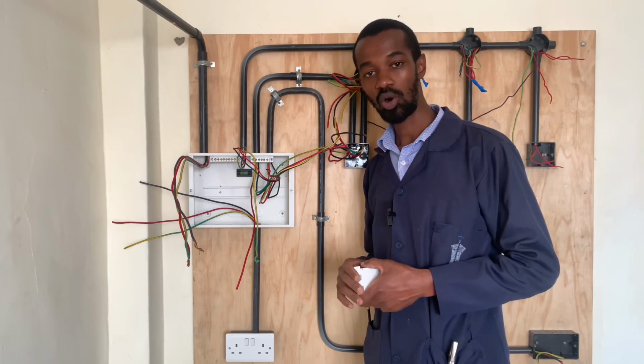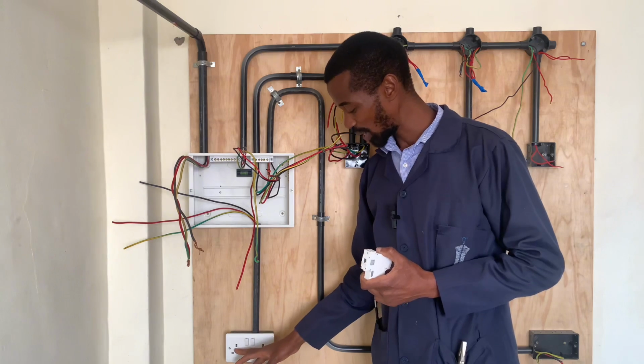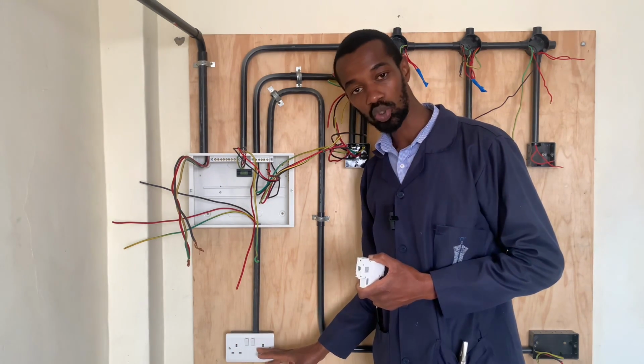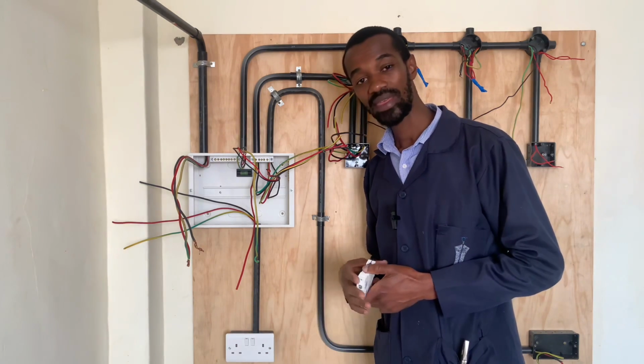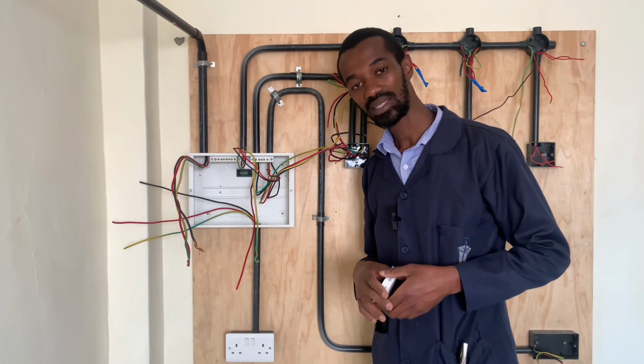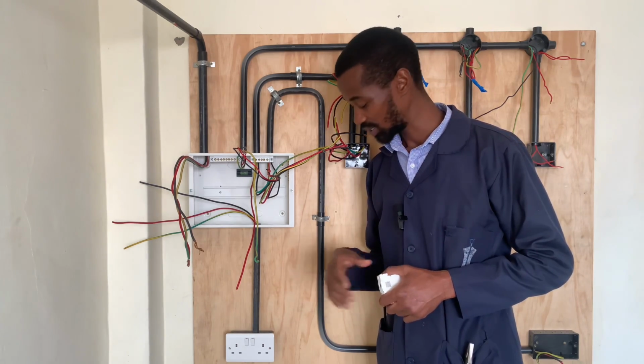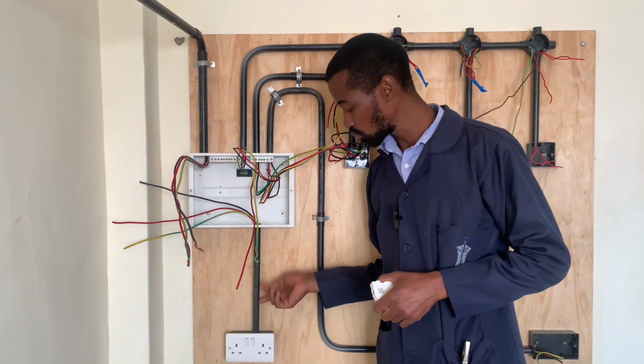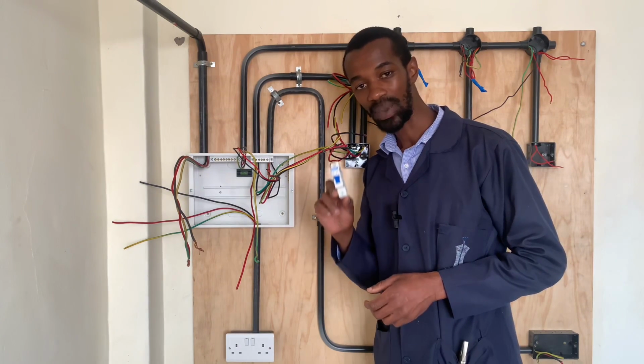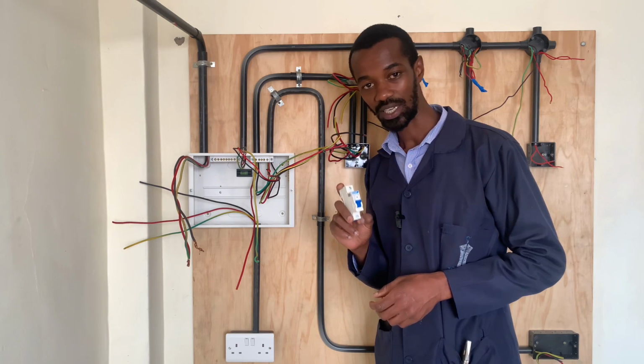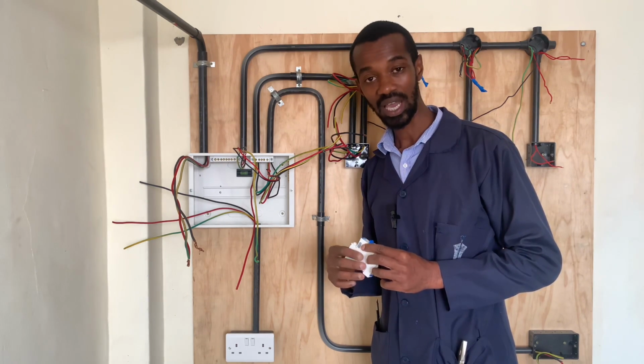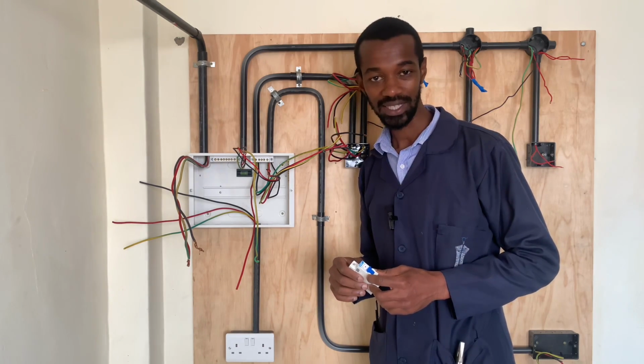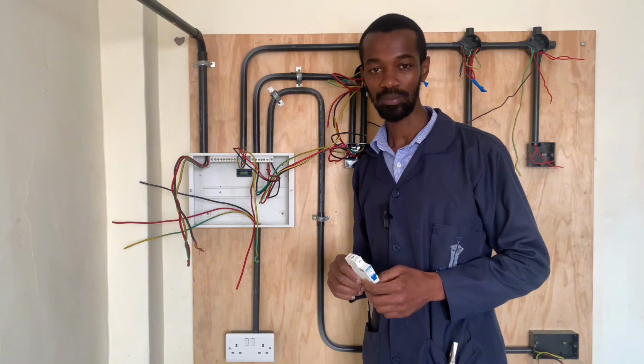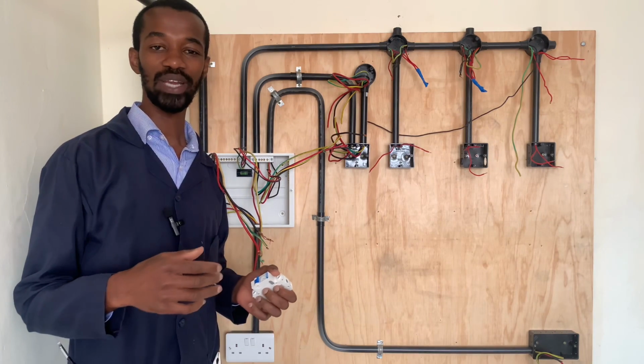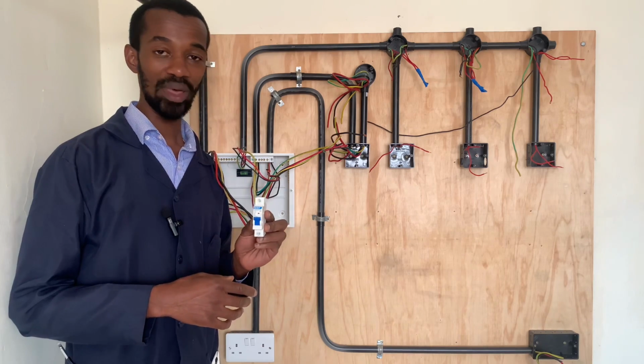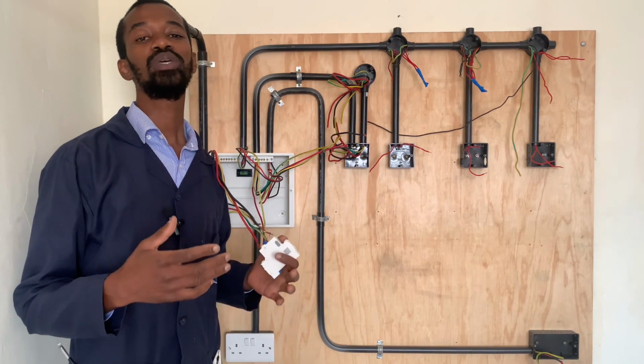The customer may decide to have a microwave on one plug and an extension cord on the other, connecting several appliances that draw a lot of current, and all that will be fed through these wires by the circuit breaker. So we must use a 32 amp MCB, since anything lower would not handle that current if all appliances are connected at once.